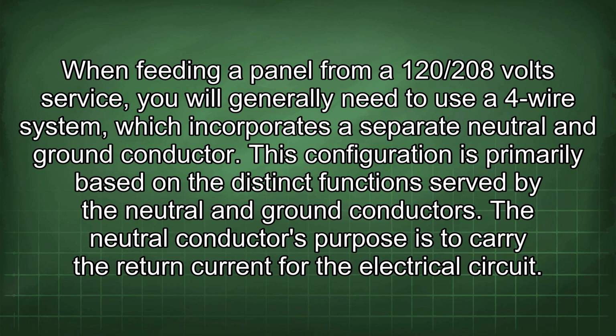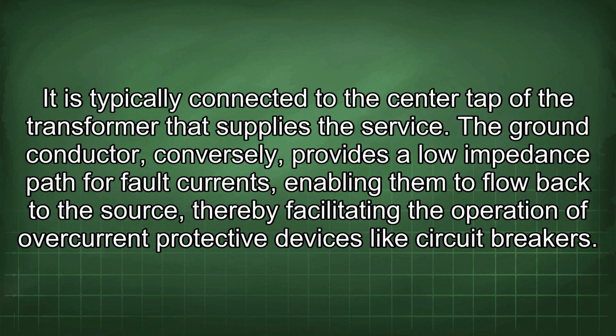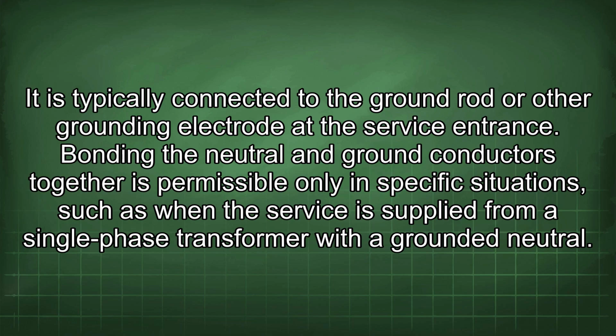The neutral conductor's purpose is to carry the return current for the electrical circuit. It is typically connected to the center tap of the transformer that supplies the service. The ground conductor, conversely, provides a low impedance path for fault currents, enabling them to flow back to the source, thereby facilitating the operation of overcurrent protective devices like circuit breakers. It is typically connected to the ground rod or other grounding electrode at the service entrance.